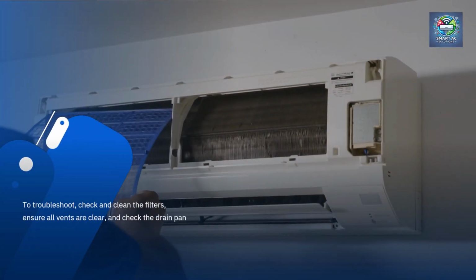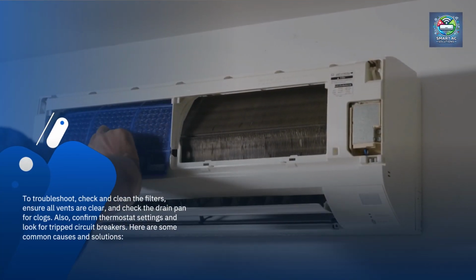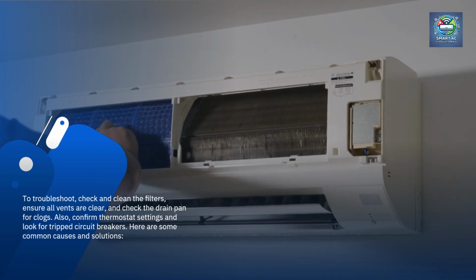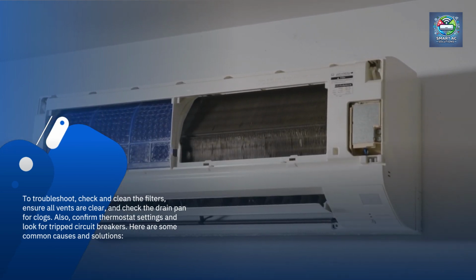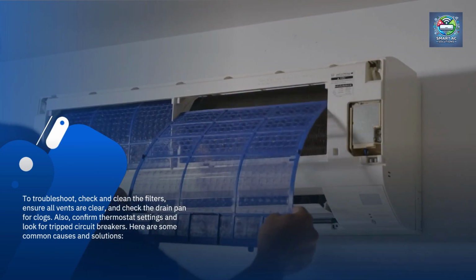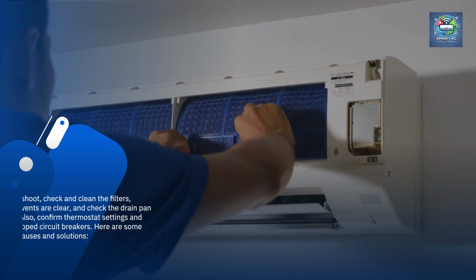To troubleshoot, check and clean the filters, ensure all vents are clear, and check the drain pan for clogs. Also, confirm thermostat settings and look for tripped circuit breakers. Here are some common causes and solutions.